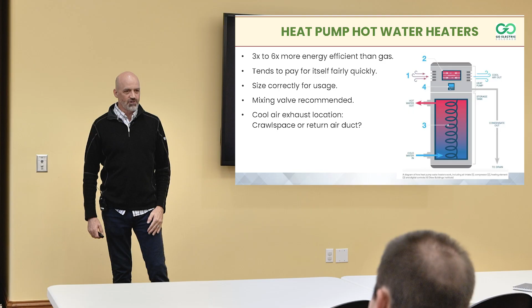And that 6 times efficiency, if you can provide a little bit of warmth to that space - if you've got another heating system, a warm area of the house, a sunny spot, or something near your mechanical room that already has some heat - that's when that efficiency goes up. I've gotten that directly from the engineers at Rheem. They say if you can provide 90-degree air to that device, you're going to be 600% efficient. Bonkers. It's awesome, love it.